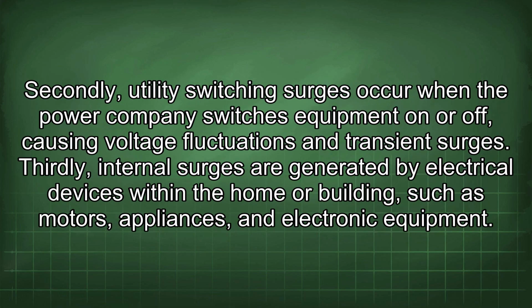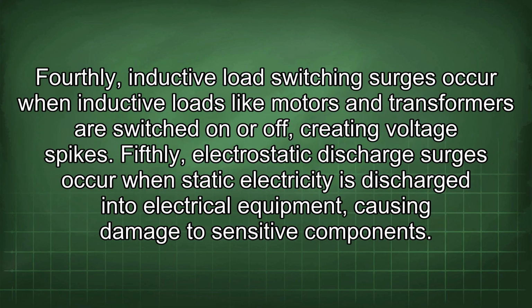Secondly, utility switching surges occur when the power company switches equipment on or off, causing voltage fluctuations and transient surges. Thirdly, internal surges are generated by electrical devices within the home or building, such as motors, appliances, and electronic equipment. Fourthly, inductive load switching surges occur when inductive loads like motors and transformers are switched on or off, creating voltage spikes. Fifthly, electrostatic discharge surges occur when static electricity is discharged into electrical equipment, causing damage to sensitive components.